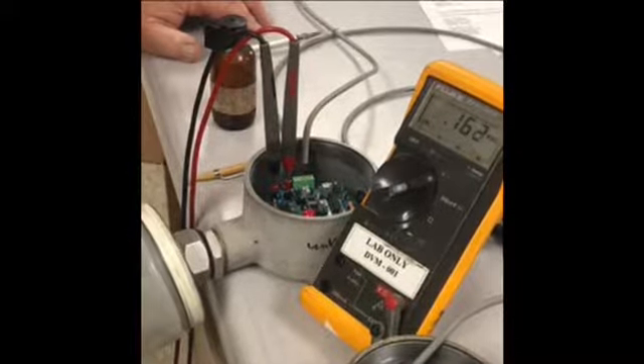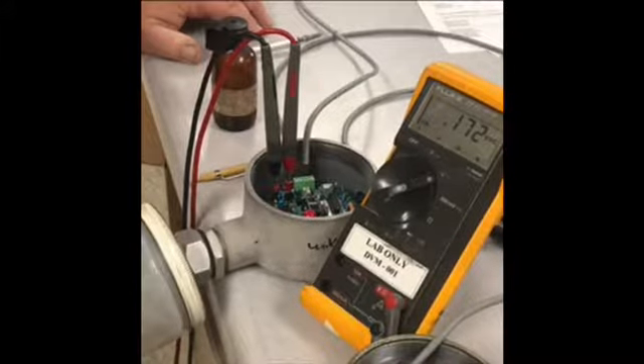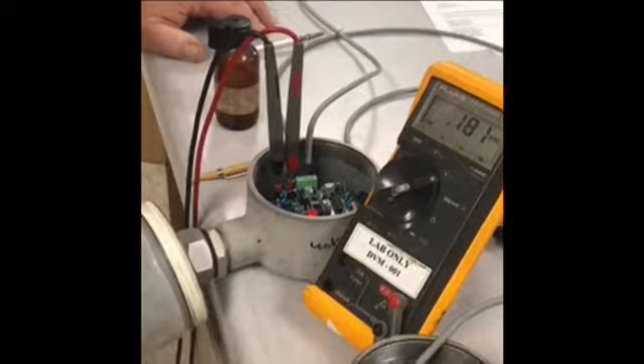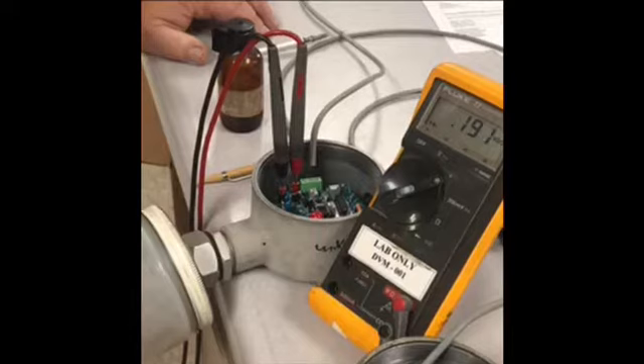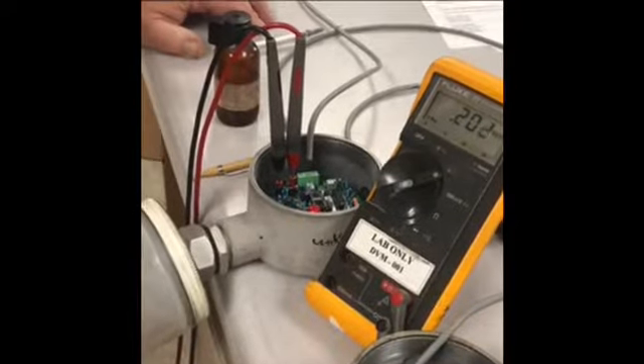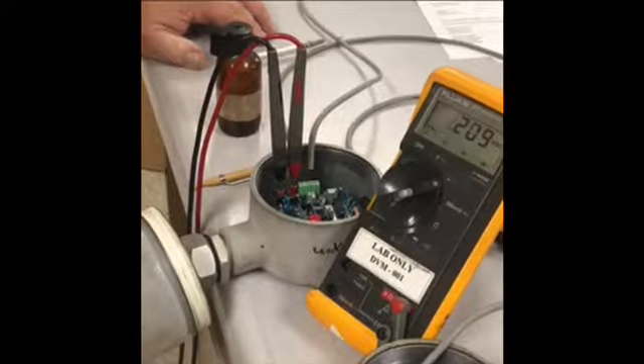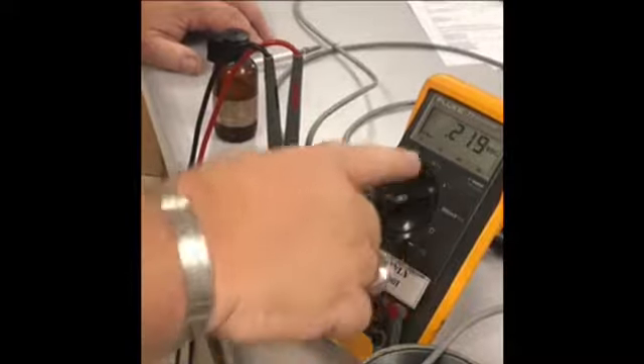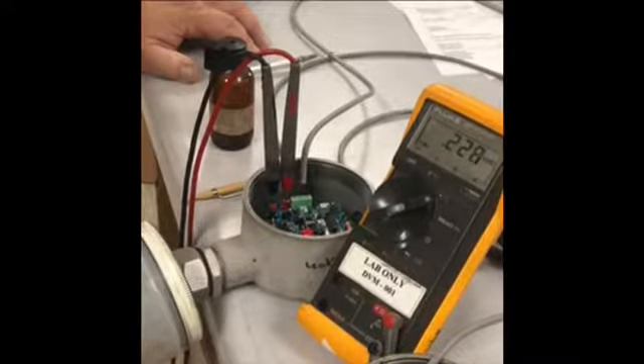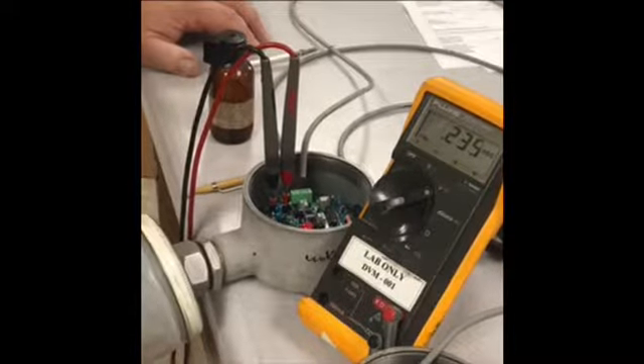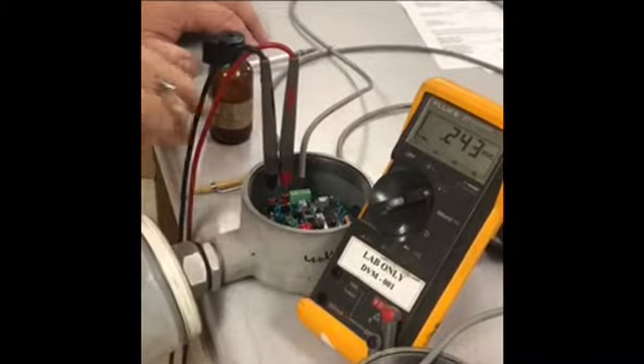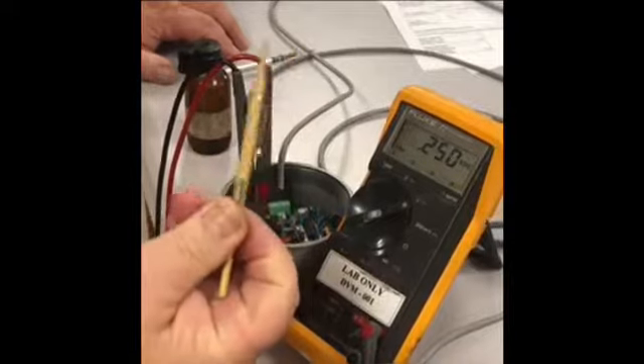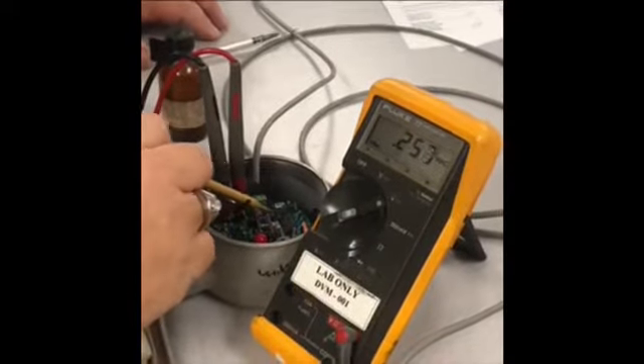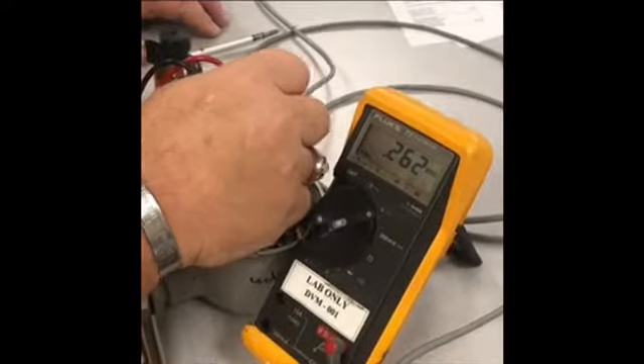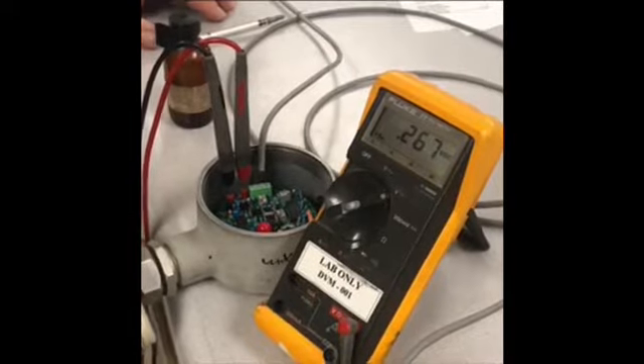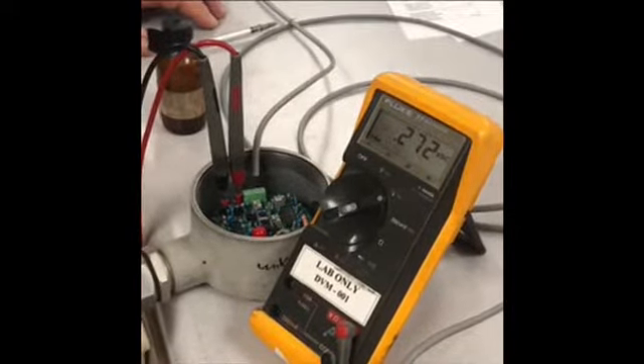As you can see by looking at the voltmeter, it's starting to go up. It's continuing to go up. It's responding to the gas pretty well, actually. So once we reach a stabilized condition, when I say stabilized, it might tick very slowly. It keeps going, 0.001, 0.002. That's not stabilized. It'll slow down much slower than that once it becomes a stabilized reading. Once it does become a stabilized reading, you're going to use your screwdriver with the flathead side. You're going to locate the span potentiometer over here, and you're going to turn this span potentiometer whichever way necessary to be at 0.4 volts. 0.4 volts is a full scale reading.